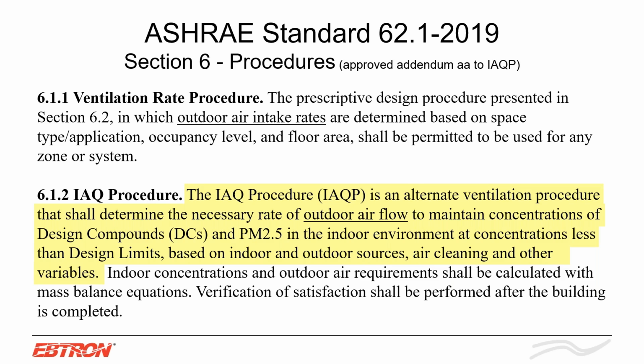For the IAQ procedure, we typically see this in lab types of applications, but if you are designing to the IAQ procedure, it's even more critical to measure airflow, because a lot of times you're decreasing your airflow rates in the space because you have some other type of filtration, albeit specialized filtration, that is removing some of those contaminants as well. Also, your design for the IAQ procedure might be trying to downsize your equipment, since there's less load and you have to bring in less outside air.